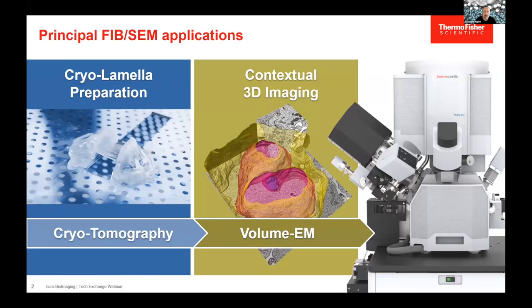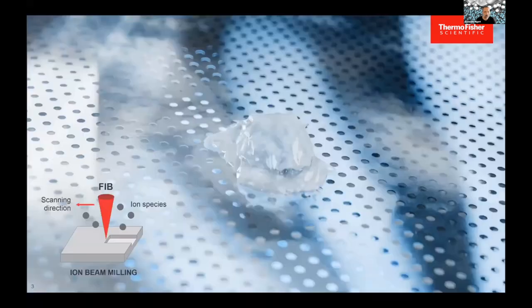Let's start with the principal FIB-SEM applications that we have and support with our dual beam or FIB-SEM microscopes. One big area is cryo-tomography sample preparation — everything where we try to thin down samples for electron tomography. Cryo-EM sample preparation means preparing lamella samples from vitreously frozen samples. There's also a second block that became more popular in recent years: volume EM, or contextual imaging, not at the high resolution offered by tomography but at a larger field of view, allowing imaging of more context. In tomography, the main goal is to use the system's ion beam to thin down a sample for transmission electron microscopy.